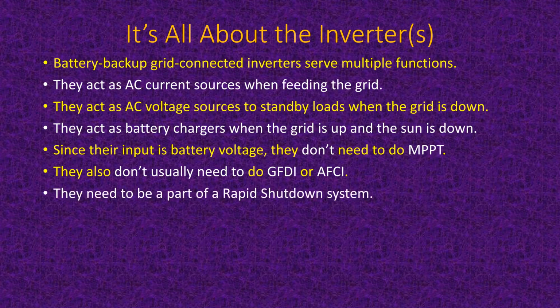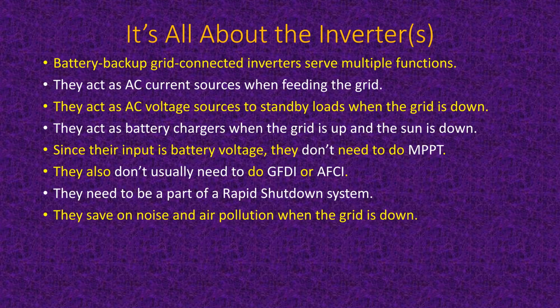They need to be a part of a rapid shutdown system, and there used to be some really interesting implementations of that. Right now, there are a number of very elegant systems. What this means is if the fire department comes out and decides that they want safety up on the roof, they don't want a bunch of 450 volt DC running around down the house. They want to be able to shut it down at the location of the system on the roof. They flip one switch and it shuts down. So these inverters need to be a part of that process so that they'll shut down if the rapid shutdown switch is hit. And we'll talk a little bit about that.